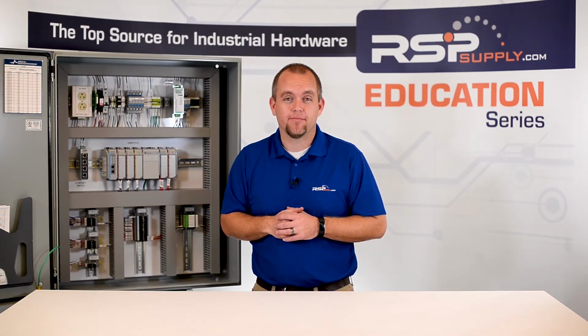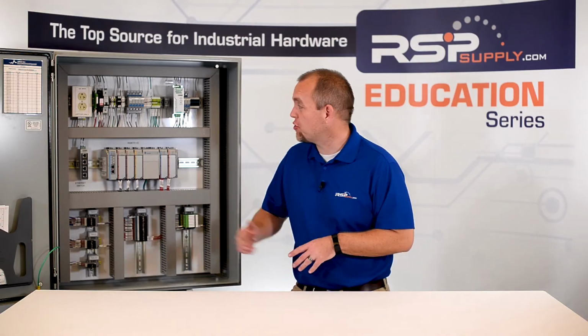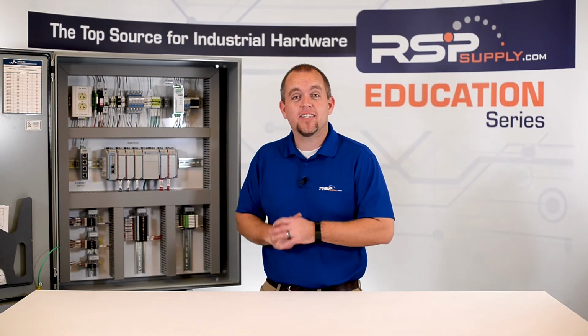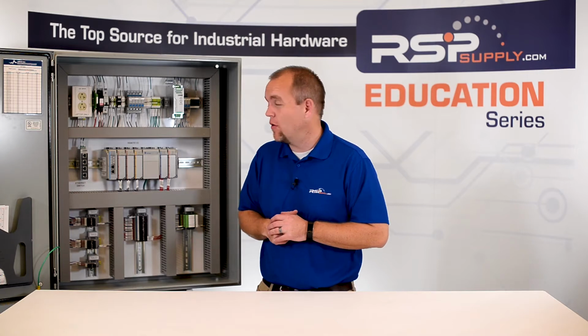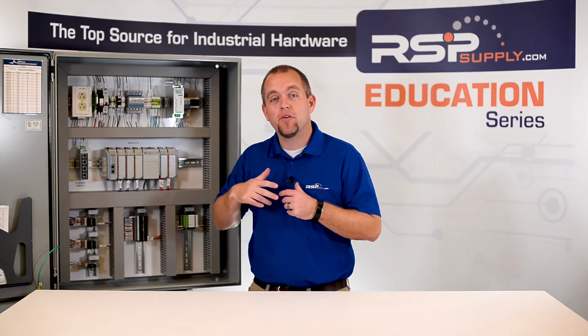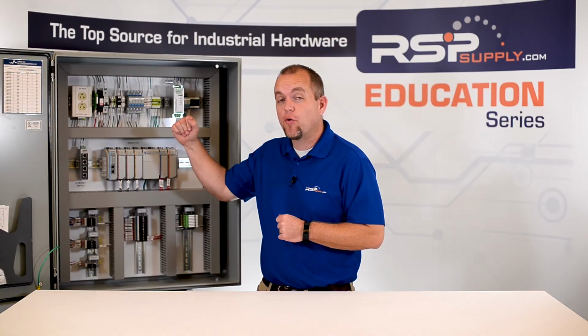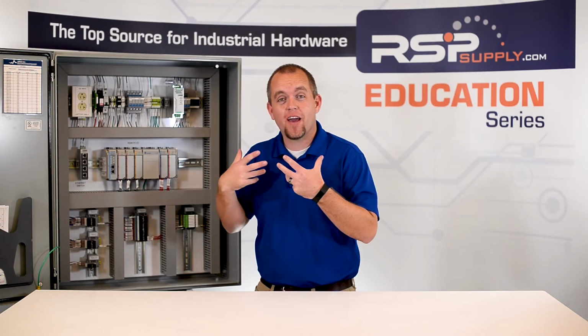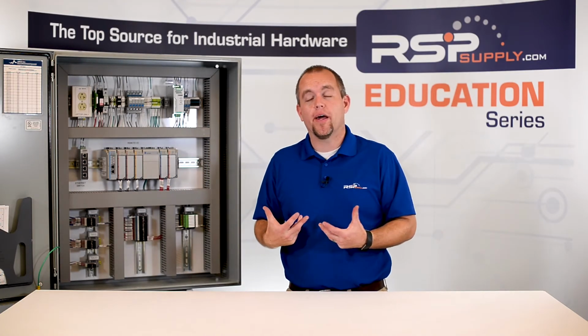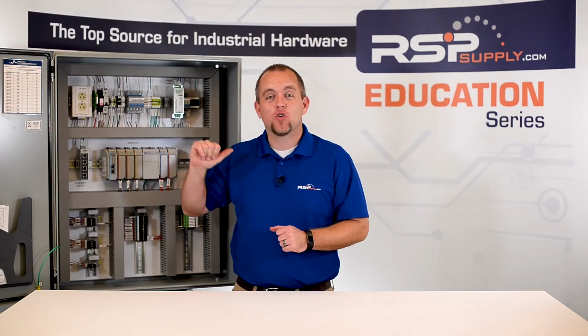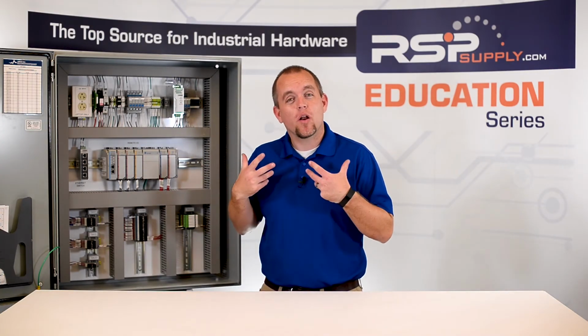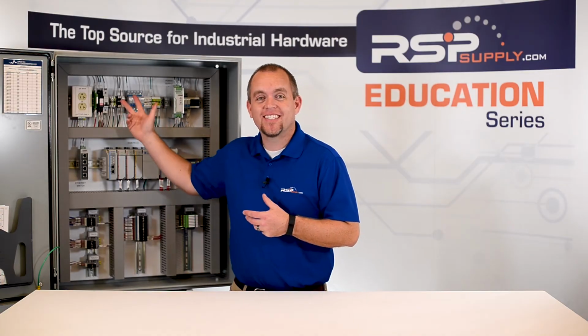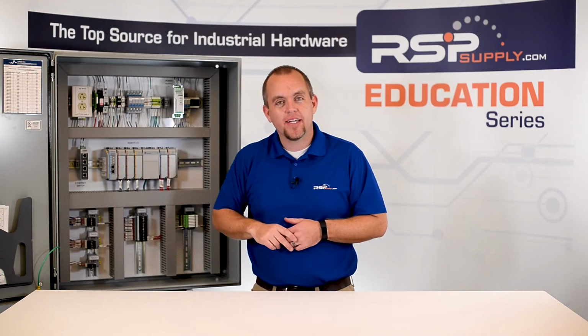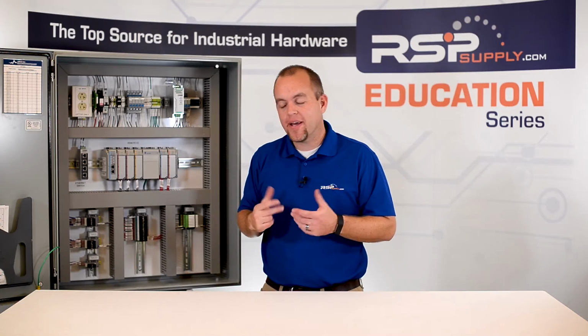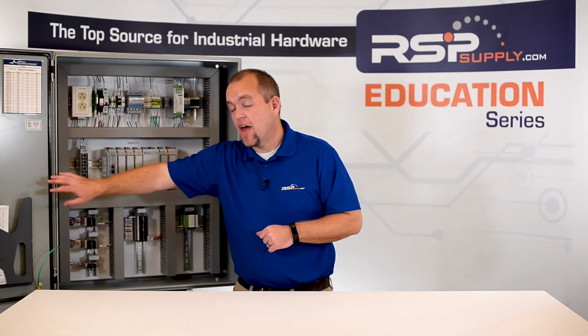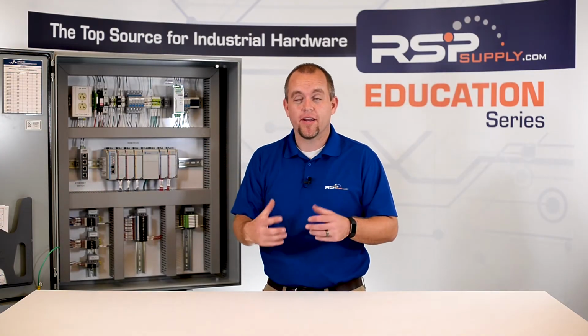Next, in power distribution, we want to make sure that we have proper grounding. This is critical to any industrial control panel. We want to make sure that we have a main grounding bus that all of our devices can be grounded to. We also want to make sure that if we have DC negative within our industrial control panel, that we tie that DC negative bus directly to our grounding bus. We also want to make sure that our grounding bus is tied to our main ground coming into the panel itself.